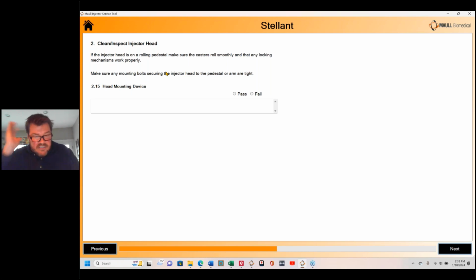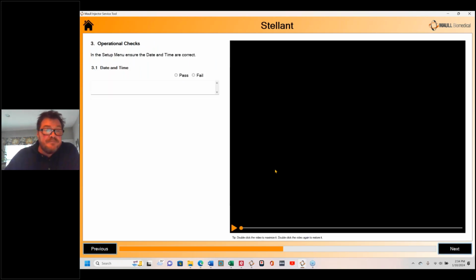Now, contrast injectors, they can be either wall mounted or ceiling mounted or on a pedestal. So one of the very first questions way back at the beginning was, it asked what kind of mounting device this was. Is it head, or is it ceiling, is it pedestal, things like that. So the head mounting device, this is just sort of generic. Whatever kind of head mounting device you're using, that's why we don't have a video for this one, because it could be 3 different things. But it's the mounting device. We're just making sure the mounting device is clean, all the bolts are secure. If it's a pedestal, make sure that the casters move freely and none of them binding up and things like that. So we'll just put pass for that one.